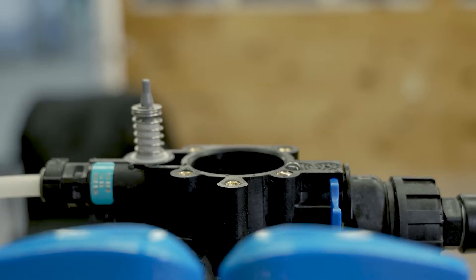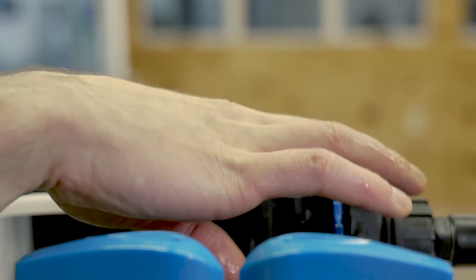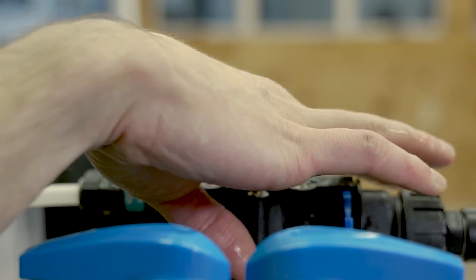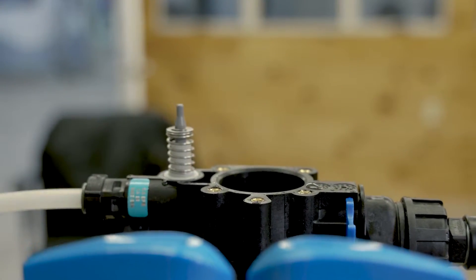When putting the seals and spacers back in, you're going to start with a seal and alternate seal, spacer, seal, spacer. Make sure to put them in one at a time and press down around the outer edge of each seal to make sure that it's seated.